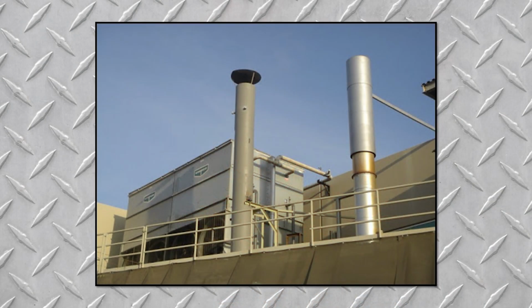Referring back to our first steam episode, it was mentioned that one of the more common ways of using waste heat is with what we call a boiler stack economizer. This uses heat from the stack to heat the feed water of the boiler and therefore reduce the amount of energy needed to create the steam. Using an economizer can save an estimated 5 to 10% of the energy required for the steam. Although these devices are implemented regularly, we still come across many places where they're not being utilized, but it makes a good thing to look for and provides for very quick paybacks.